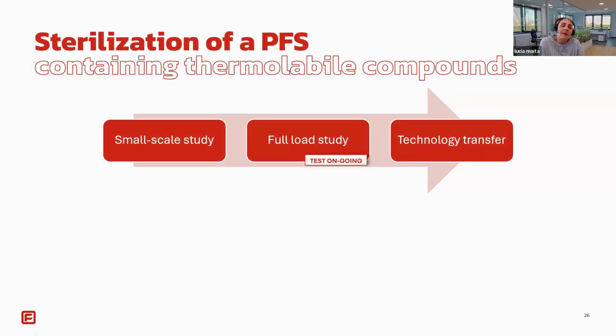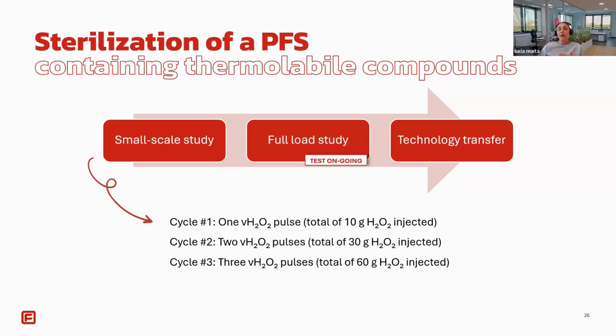Okay, the process was developed through a stepwise approach. So we start with small scale testing and we perform different sterilization cycles. We test different conditions. We change the number of H2O2 pulses and the total amount of H2O2 used for the sterilization, so the total amount of H2O2 injected during the sterilization stage. And based on these results, the optimized process is now being verified at full scale, with the final transfer to the customer equipment planned as the next step.